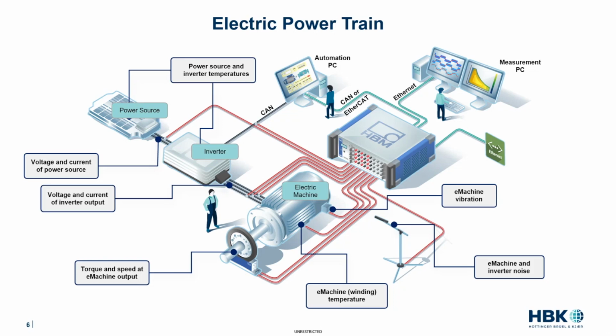And some of our customers are also interested in measuring vibration signals or acoustic noise signals generated by, of course, the high frequency components which come from the inverter, for example, but also mechanical oscillations coming from the mechanical drivetrain. There are a lot of different sources which create vibration and acoustic noise. And the challenge is to measure all those signals time synchronously in order to be able to do further analysis on that, which helps to optimize the drivetrain. And now, in the first step, since we are talking about electric power measurement today, I will discuss how to measure current and voltage correctly in a suitable way.